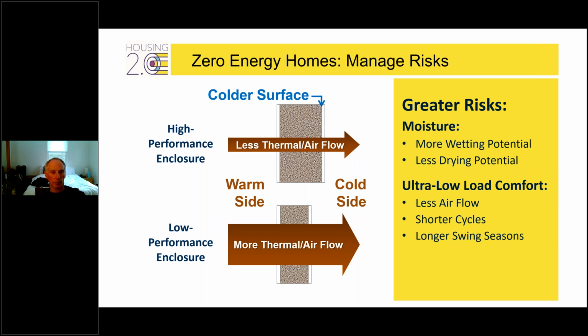Shorter cycles in the summer, because the sensible loads are so small, mean we get less accidental dehumidification from the air conditioning system. So will we have enough latent load management to keep humidity under control? Similarly, on the front and back ends of the seasons, they shrink because the sensible loads are so much lower in ultra low load homes. So we have no air conditioning for an extended time, maybe into May or June, and it shuts off earlier at the end of summer. What happens in those swing seasons to manage the latent loads that are still there? So comfort is a bigger risk in zero energy homes.